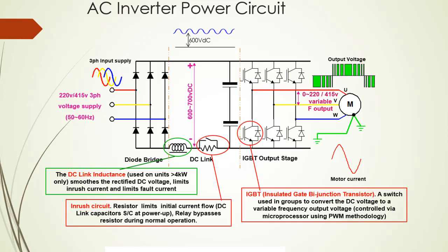This generates the AC current system for the motors in the AC inverter power circuit. In the diagram for the AC inverter power circuit, there is a 220V or 415V three-phase voltage supply at 50 or 60 Hz. There is the diode bridge used for rectification — AC to DC. The DC link inductance is used on units over 4 kilowatts only to smooth the rectified DC voltage, limit inrush current, and limit fault current.